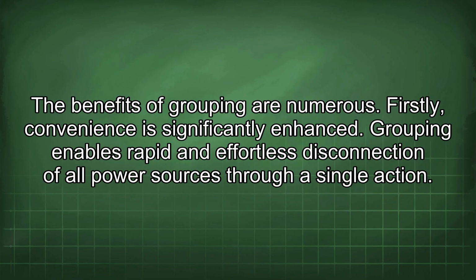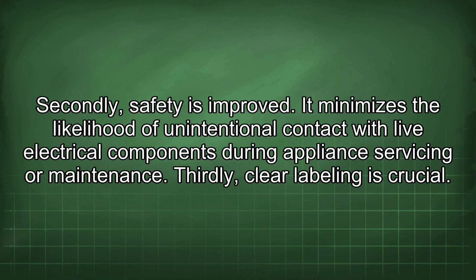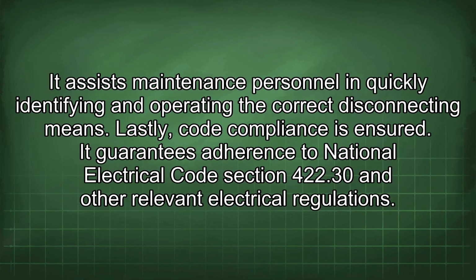The benefits of grouping are numerous. Firstly, convenience is significantly enhanced. Grouping enables rapid and effortless disconnection of all power sources through a single action. Secondly, safety is improved. It minimizes the likelihood of unintentional contact with live electrical components during appliance servicing or maintenance. Thirdly, clear labeling is crucial. It assists maintenance personnel in quickly identifying and operating the correct disconnecting means.